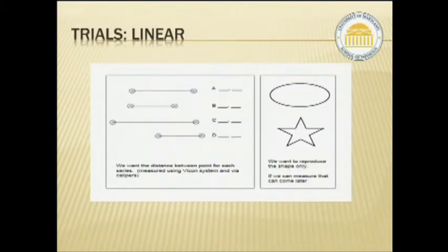And on a first pilot, arbitrarily, we created this diagram that you see here, a piece of paper, and there were these line segments, and then this oval and this star, and essentially we threw it into a laparoscopic trainer box, and then we had someone take our instrument, put it through the trainer, and literally pick the 2 points. So the first time they were told to pick the 2 ends, the 2 points, and then our system calculated the distances.